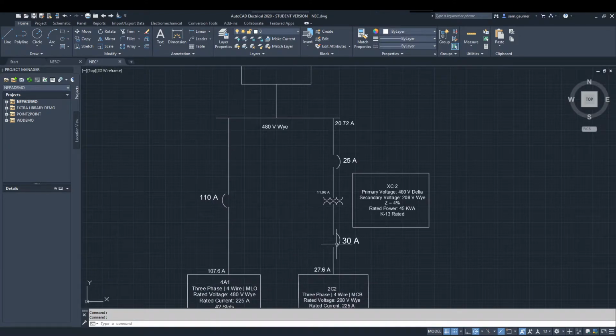My mentality for these was I wanted them to be low, or just slightly above the rated amperage, but below 1.25 times the rated amperage, because that's where we'll be speccing our wires towards.